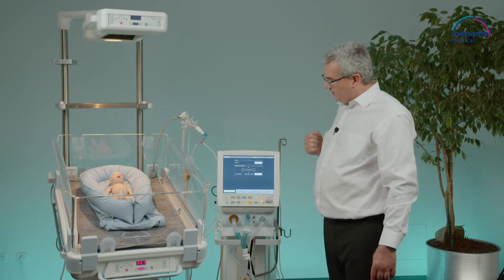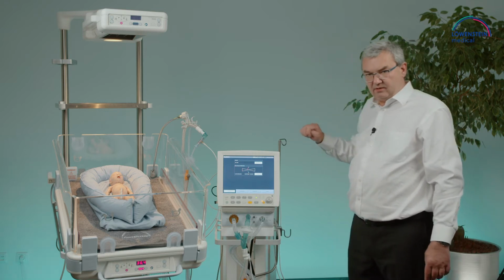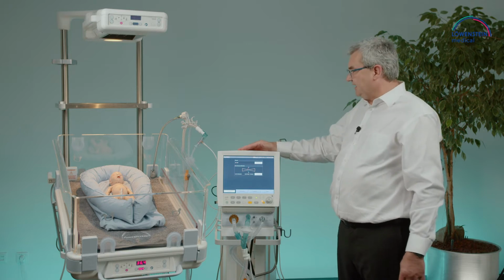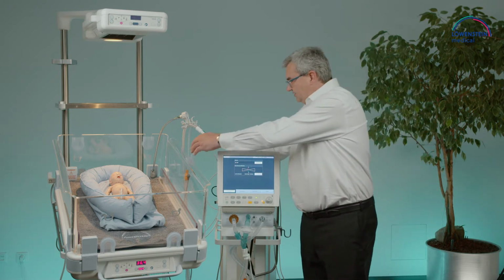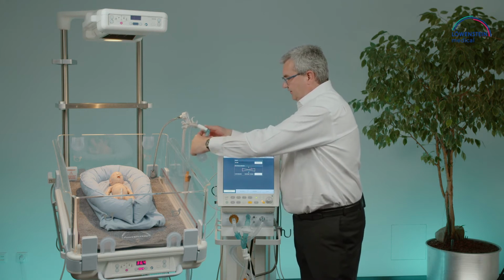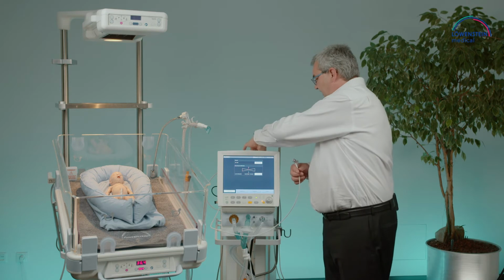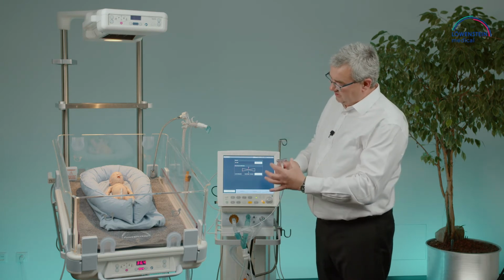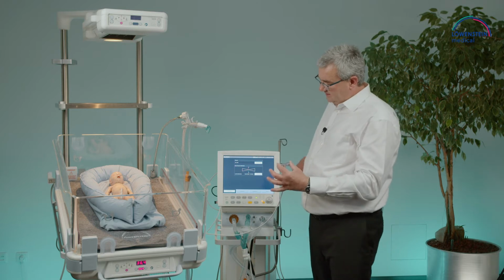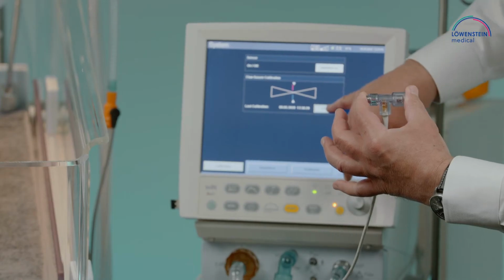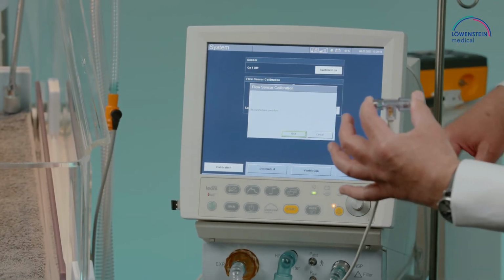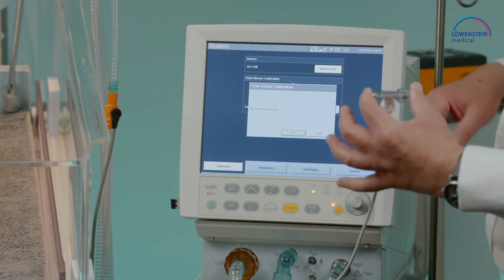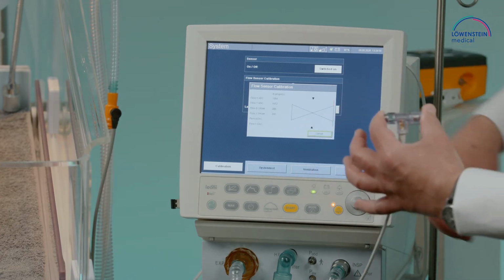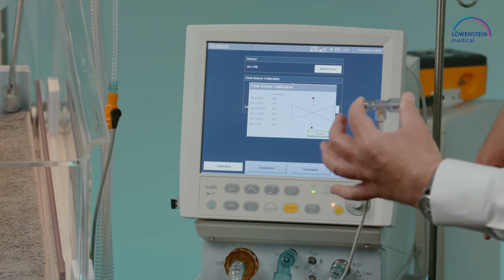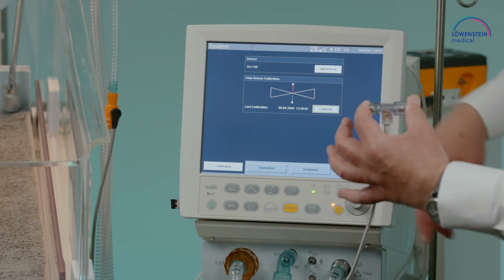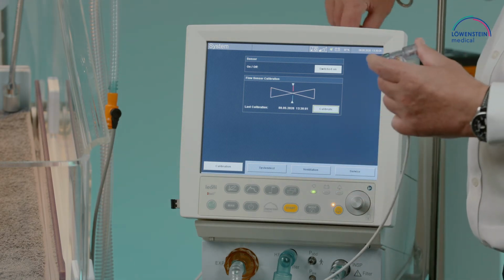So we see here the calibration screen actually has started the calibration of the internal oxygen cell. The system is always doing the calibration of the oxygen cell automatically. To do the calibration of the flow sensor, it's important to close the flow sensor from two sides to prevent flow appearing on the screen. We can see here, and we have to confirm next, the message: be sure to have zero flow. We confirm yes. Now the system works out the calibration, prompts with close. You close, and by that you have finalized the calibration.